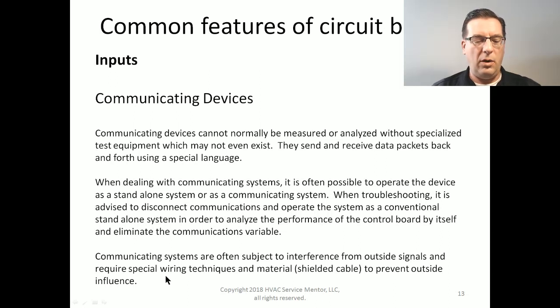Another thing you should know about communicating systems is that they can sometimes be subject to interference from outside signals, and they sometimes require special wiring techniques and a special cable to prevent outside influence. If it's a system that requires that and it got installed with normal brown thermostat wire, that could be part of the problem. And so I look to see, it's going to be in the installation manual, whether or not your unit needed special cable and whether or not it's there. And if it's not there, get it there first, and then maybe all of your communication problems will go away.